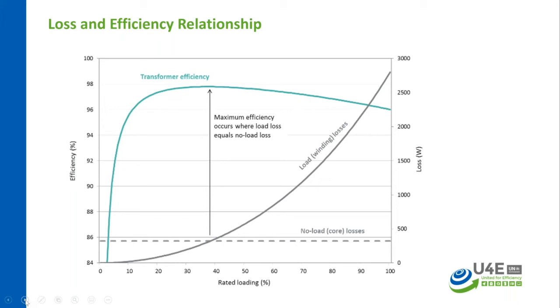So particularly for urban power infrastructure, the need is for a compact transformer which generates less heat so that you don't need a big cooling system for this transformer. And if you plot the efficiency curve, you can find that the efficiency is generally at the maximum at 40 to 50% of the load, sometimes even at a lower load percentage. And there are technical solutions available to improve the efficiency performance with different materials and different design options. And there is a new generation of materials which can reduce the no load losses even further. There are ways and means which OEMs know to comply with the regulation requirement without investing in additional manufacturing infrastructure, but just by changing the design.